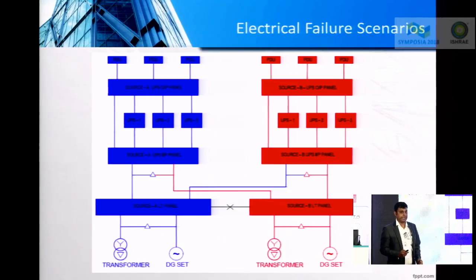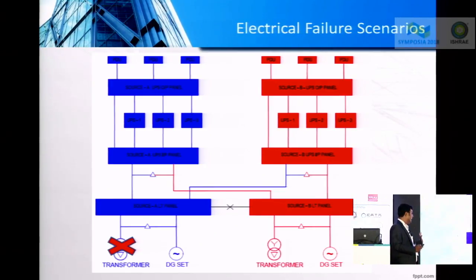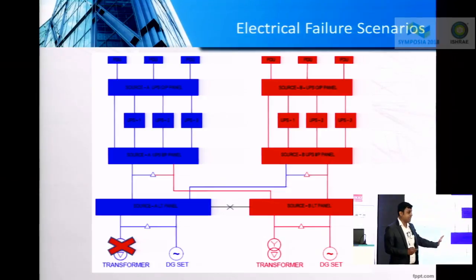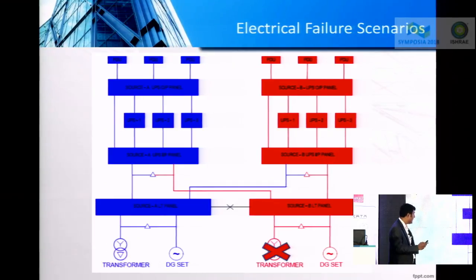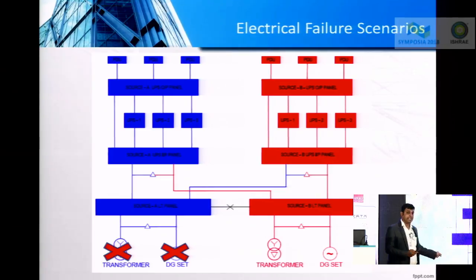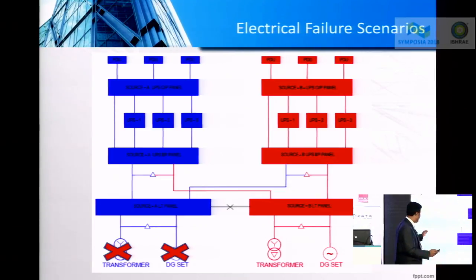What we can do during the integrated system test is fail the source A transformer and see that the entire load of source A gets transferred from transformer to DG. During this transfer, the UPS will go into battery mode for a moment, let's say for 30-40 seconds. However, there should be no impact on your UPS output supply. Similarly, I can create a scenario by failing the source B transformer and see a changeover from source B transformer to source B generator. I can create a complete failure of source A by failing the transformer.